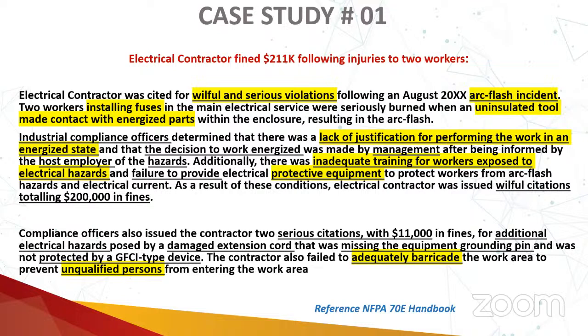Otherwise, we cannot justify working on the live state just because establishing an electrically safe work condition will cost us a huge loss in production. It's not feasible to take the shutdown right now due to X, Y, and Z reasons, etc. Those justifications need to be aligned with the Article 110.4 exemption criteria. Otherwise, those justifications are not acceptable.